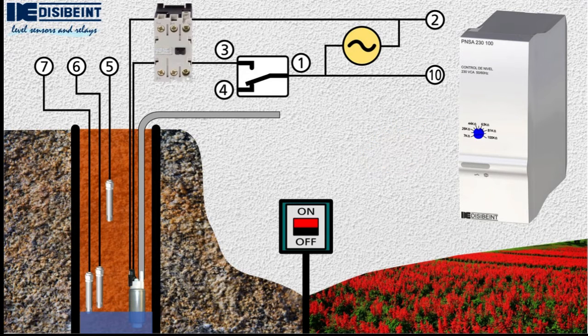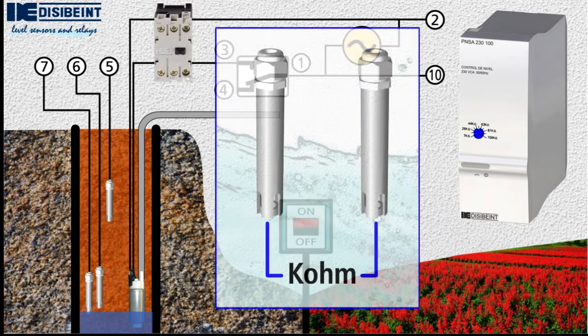The operation of level relays is based on the conductivity of the liquid they are controlling. They measure the resistivity between the probes and act on a relay depending on the presence or lack of liquid.